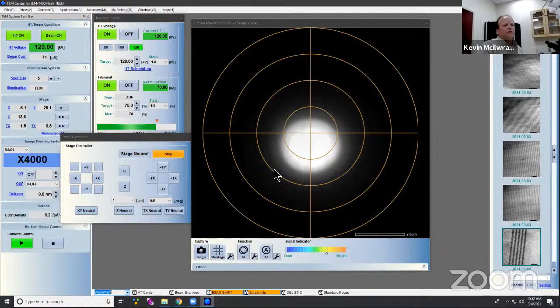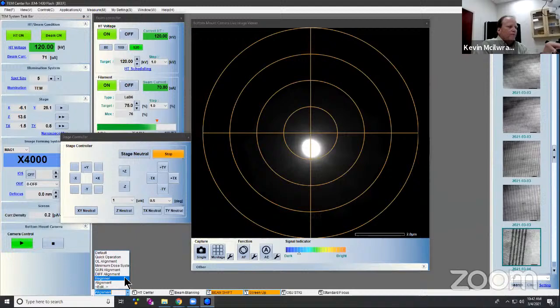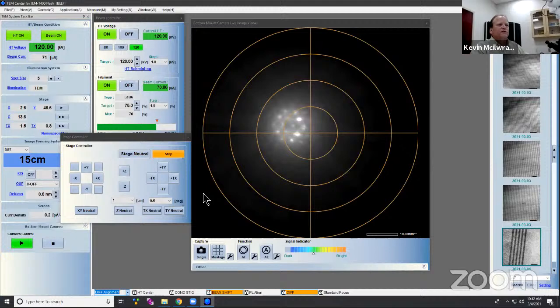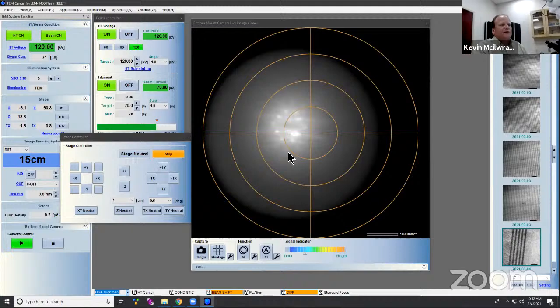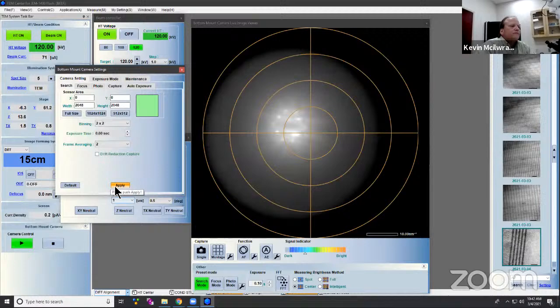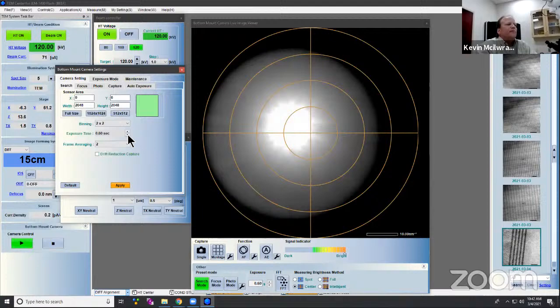So now I'm going to come down and go back to crossover. And I will switch the diffraction, but now I'm going to move the sample and go to a thicker area. So I'm starting to lose the diffraction pattern. But it's kind of interesting because for convergent beam diffraction, we start to get more of this information in the center of the image. And that was too much.